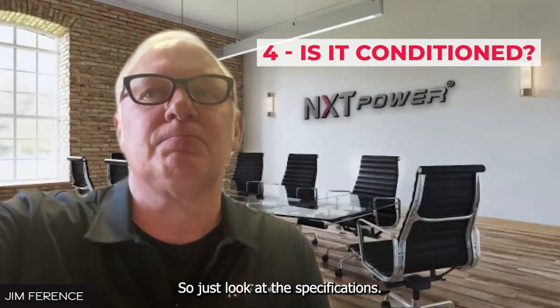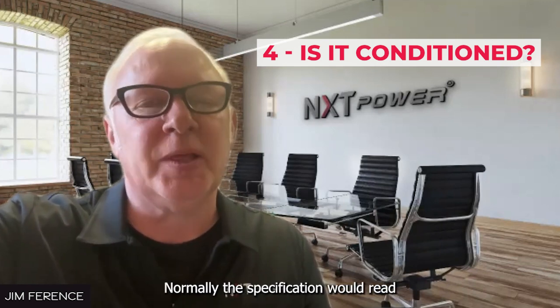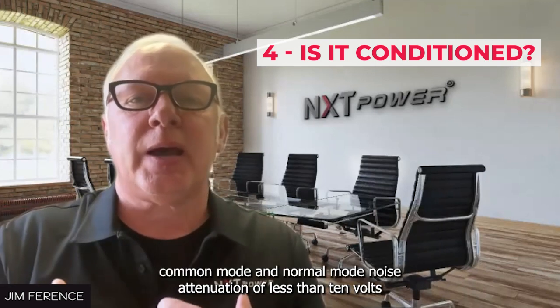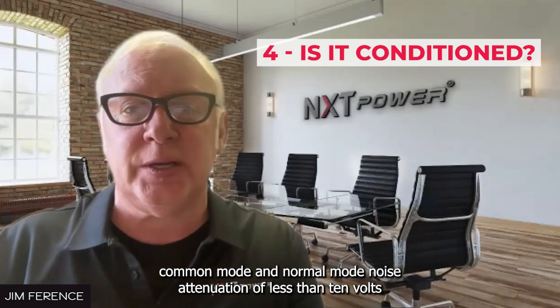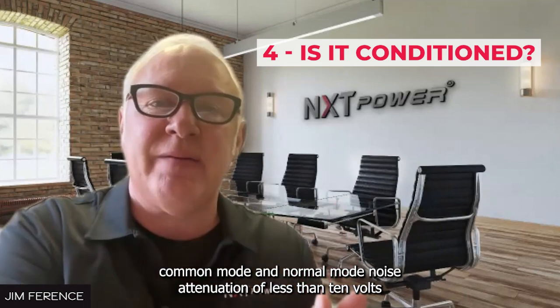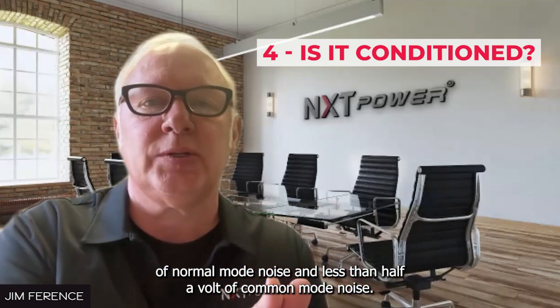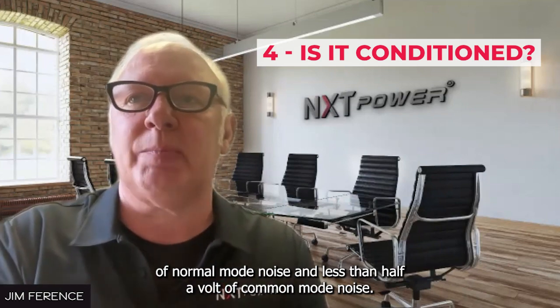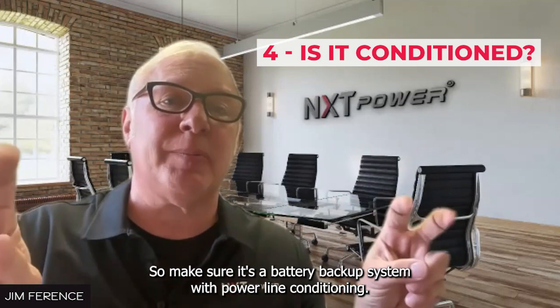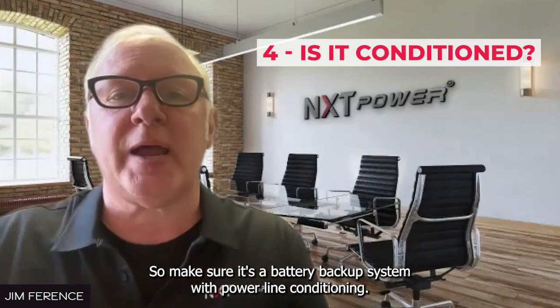Just look at the specifications. Normally the spec would read common mode and normal mode noise attenuation of less than 10 volts of normal mode noise and less than half a volt of common mode noise. So make sure it's a battery backup system with power line conditioning.